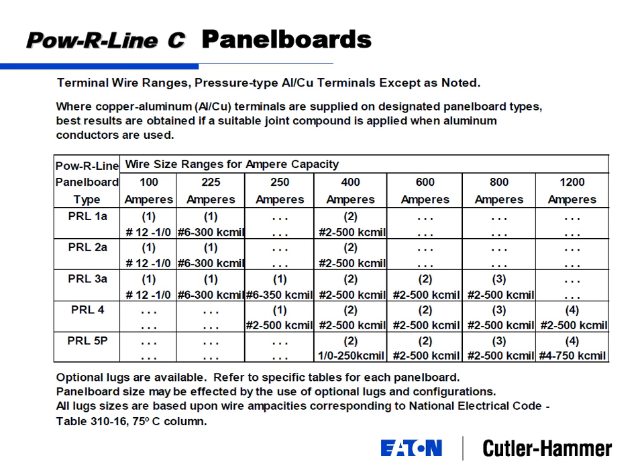whether from an engineer or an install, it's always important to double check that the cables you're pulling and the cables you want to use match a panel board main lug or main breaker that's available. Sometimes you want to oversize it, or maybe you had 4 cables per phase in one application and you're replacing the panel board and that one only takes 3 cables per phase, and that's just a bunch of different things that come into play, and it's sometimes overlooked, but just know it should always be considered.